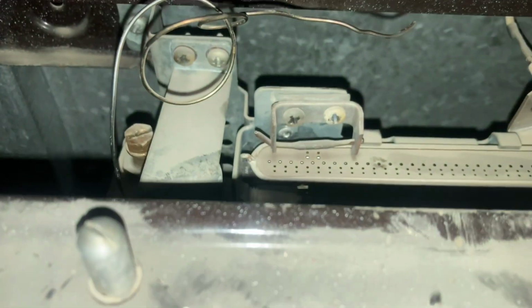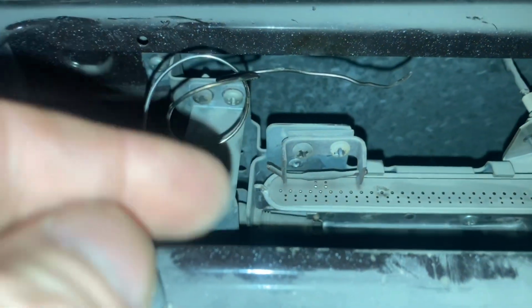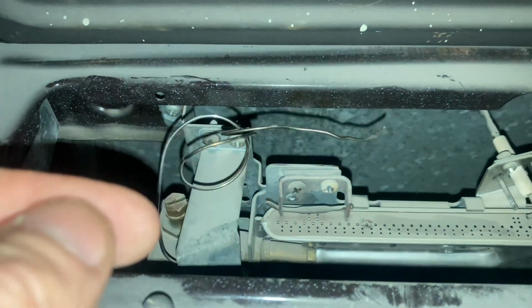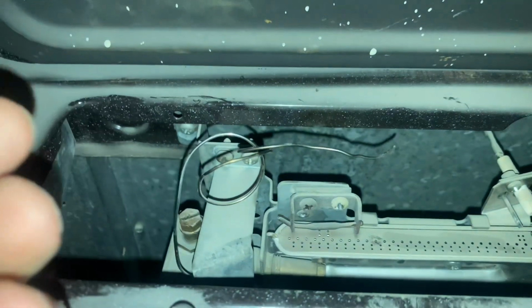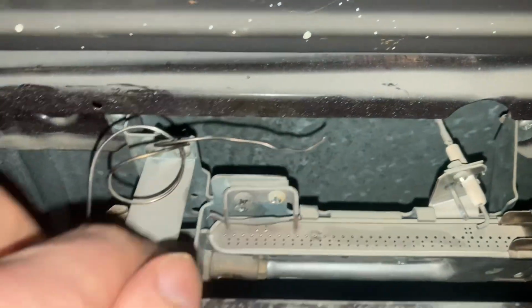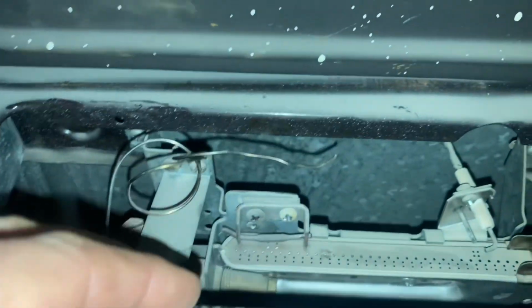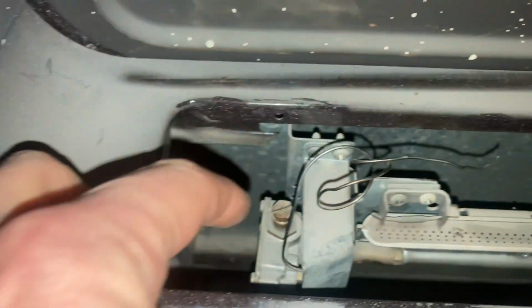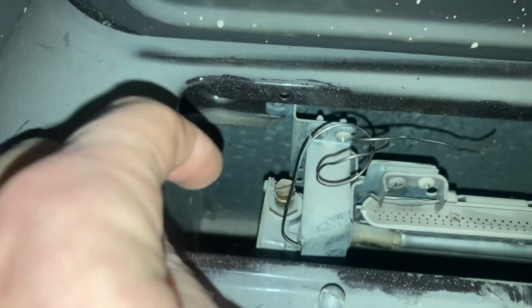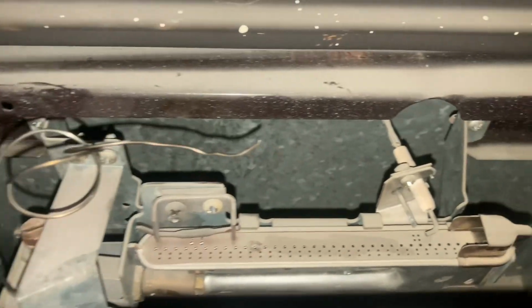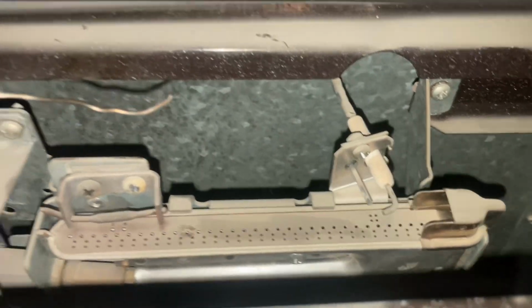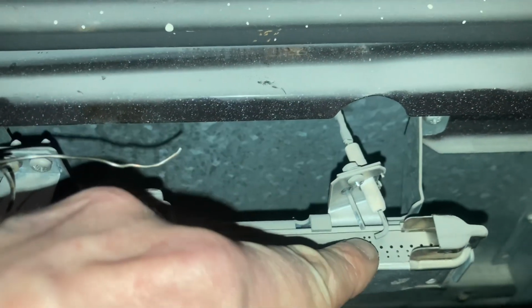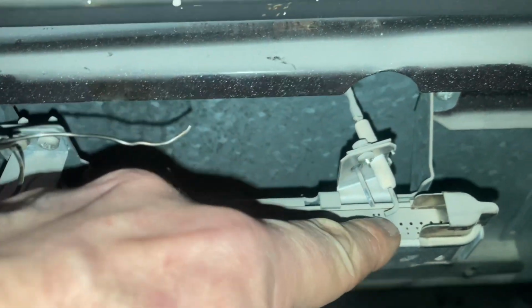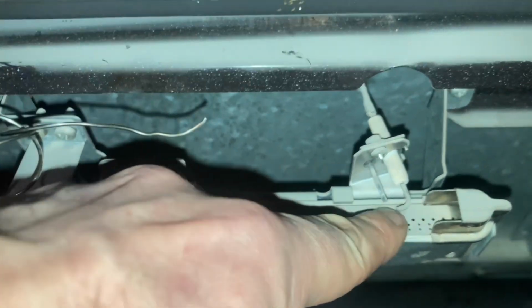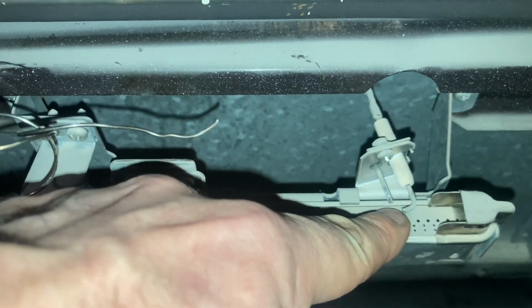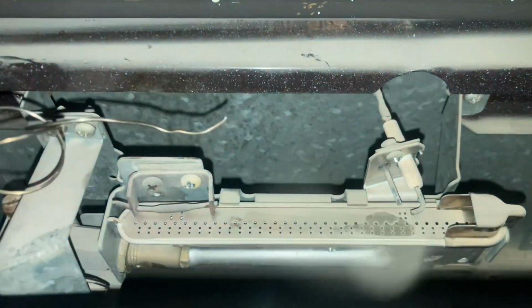Here's another flame safety device. So remember, if this goes, it'll just turn low flame. It won't lift, it won't give out any heat. So for this one, look, under the 2 screws, lift it out, and it'll be connected to the side. If it doesn't ignite, another thing you can do is just clean the gap. There could be some grease in there, oil or dirt. Just give it a bit of a clean. Clean it with a nail file or something.